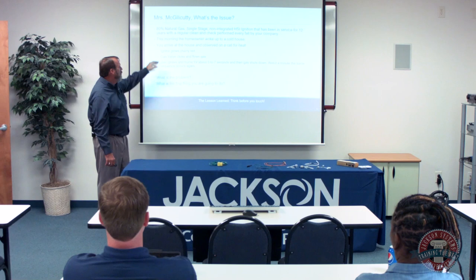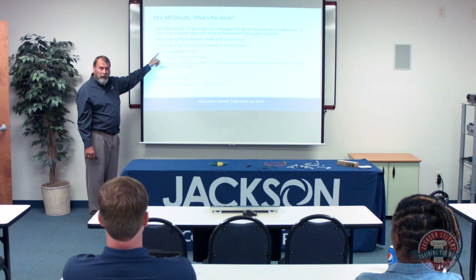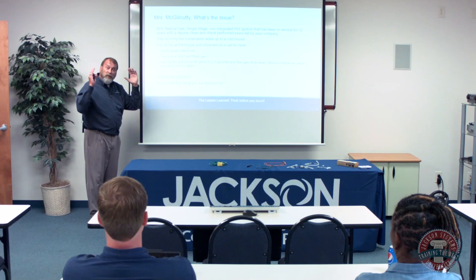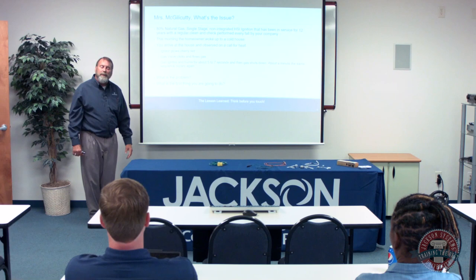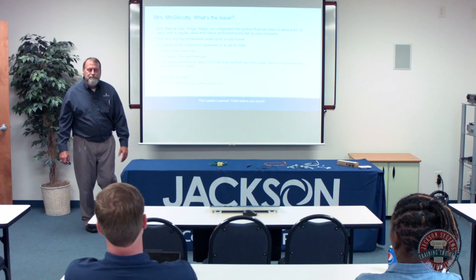It's an HSI system, so the glow bar starts burning cherry red. You hear a click, the gas valve opens, and you hear the ignition, you see the blue flame. But it only lasts for about 5 or 7 seconds. Then it goes out. What is the problem? What do you think it is?